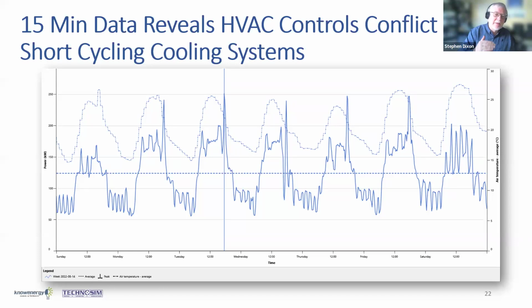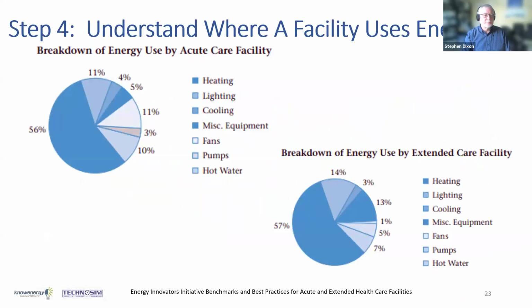The second issue was temperature control. Building temperatures in an office area were set back towards the end of the afternoon, and the electric heat kicked in to raise the temperature back to the setback temperature. That was a controls issue. One profile, 15 minutes of analysis, huge opportunities in terms of operating cost for that building.